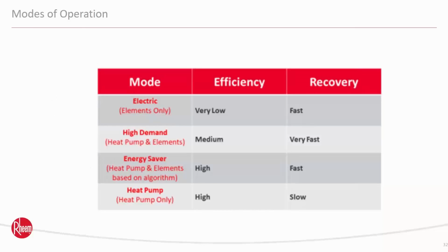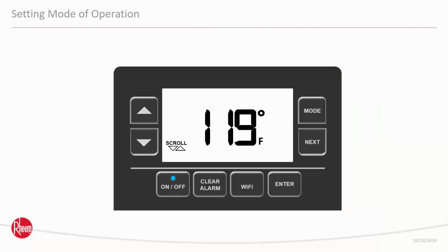Electric, here's just showing you the efficiency and recovery. Electric elements only. It's a fast recovery, but it's a low efficiency because it's a standard electric water heater. High demand, it's very fast recovery. It's going to be medium efficiency because you're using the heat pump as well. And then in your Energy Saver, your highest efficiency, like I said before, but your recovery is going to be decent. It's pretty fast actually. And heat pump only, it's going to be slow, but like I said, that's your most efficient. You're looking at pennies a day to heat that tank up.